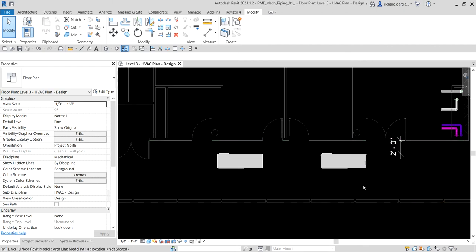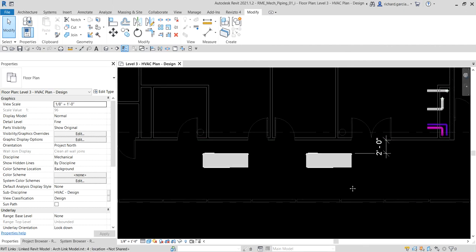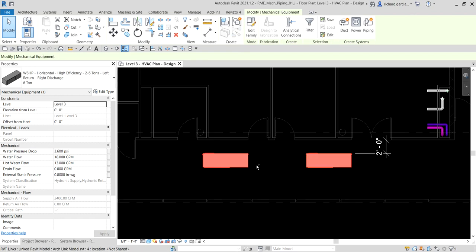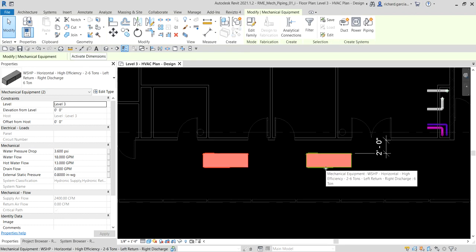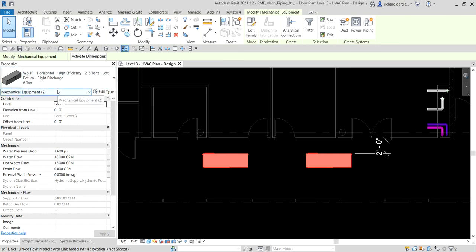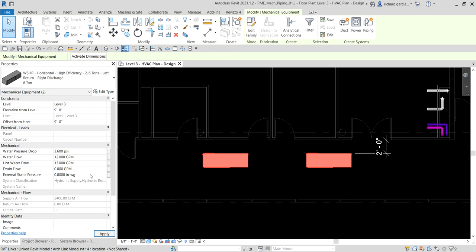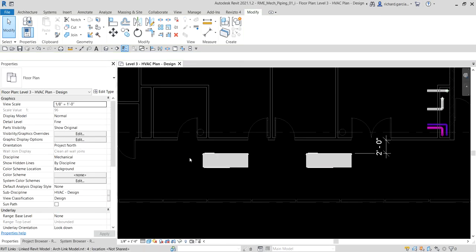Now we're going to modify our water source heat pumps. I'll select both pieces of equipment — hold Control to select the second one along with the first. In the instance properties, I'll change the offset height from zero to nine feet. Then I'll look for the water flow parameter and change it from 18 GPM to 12 GPM, then click Apply.